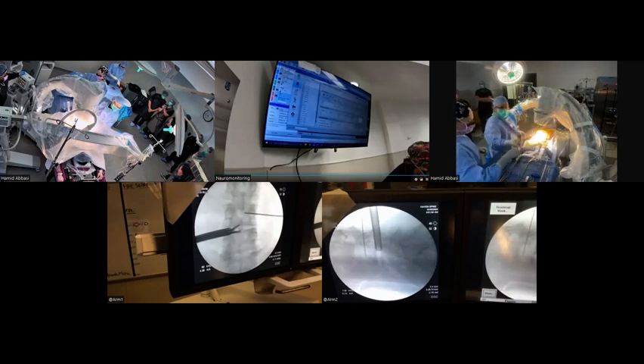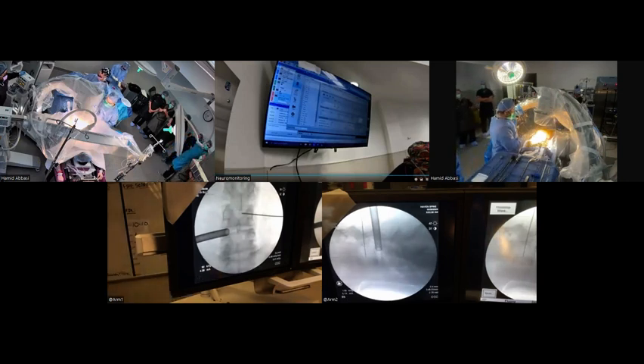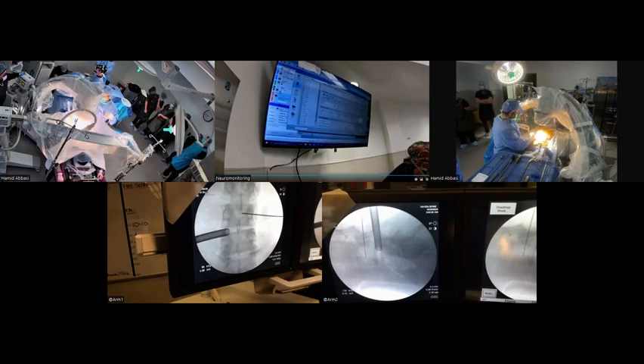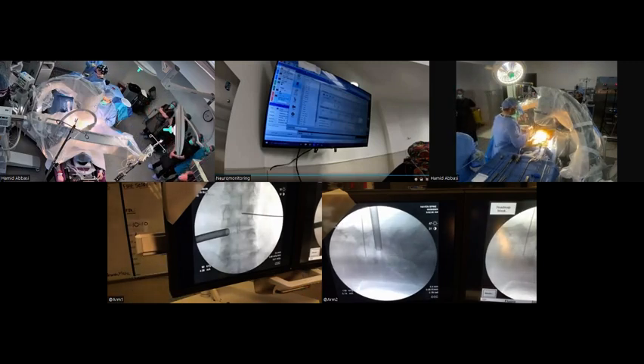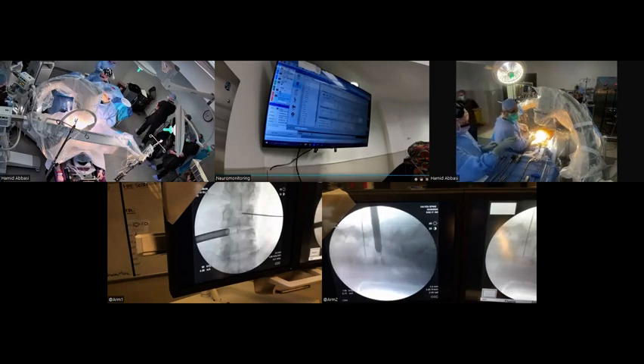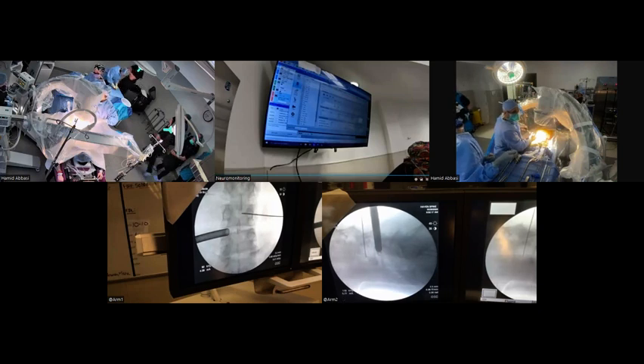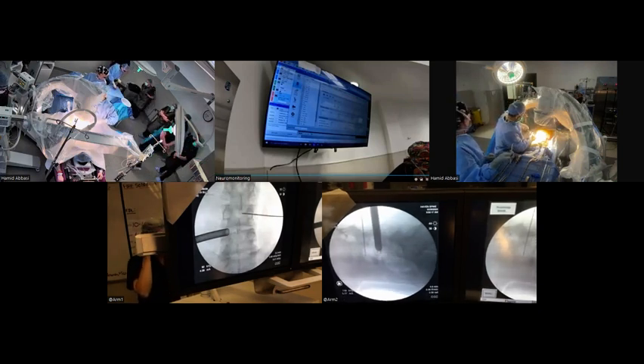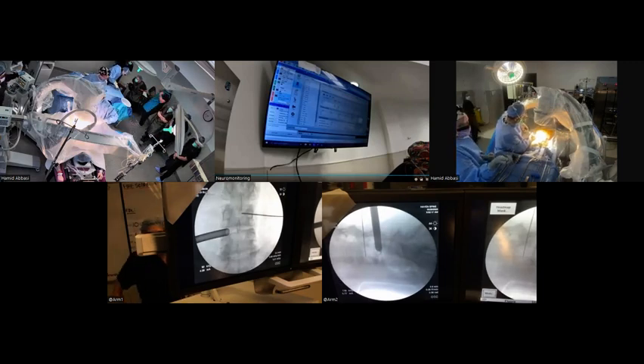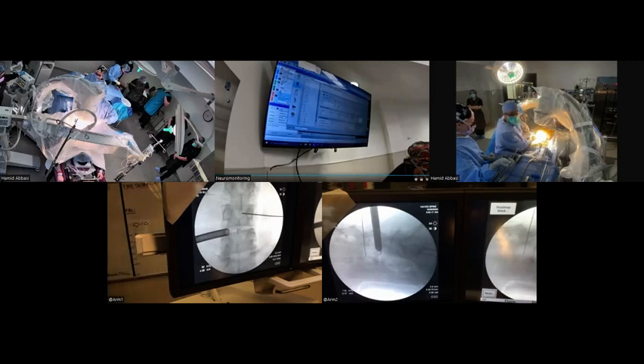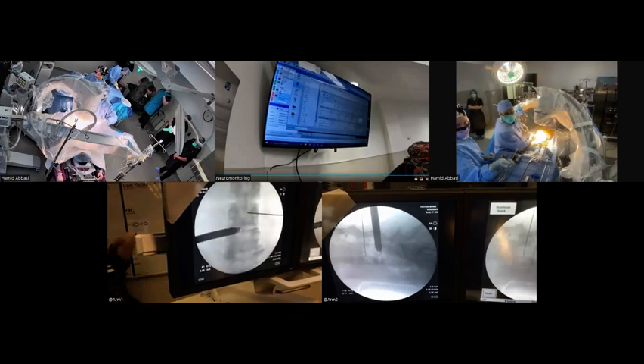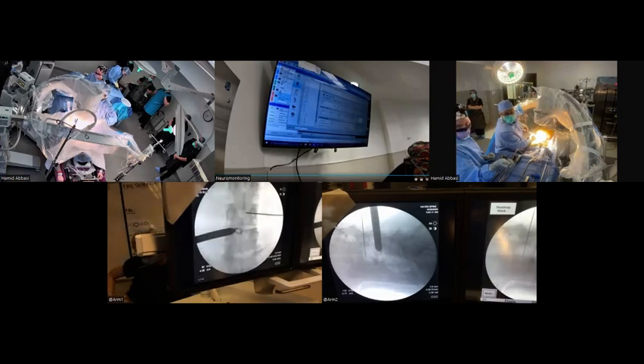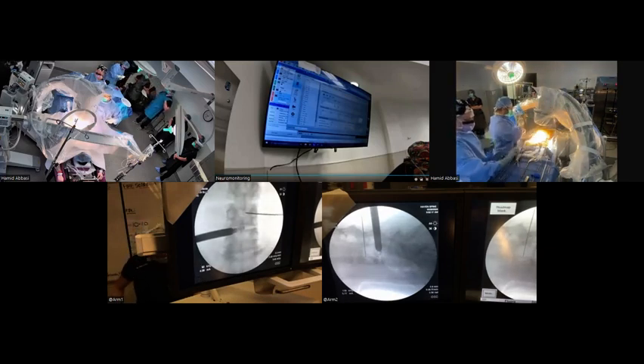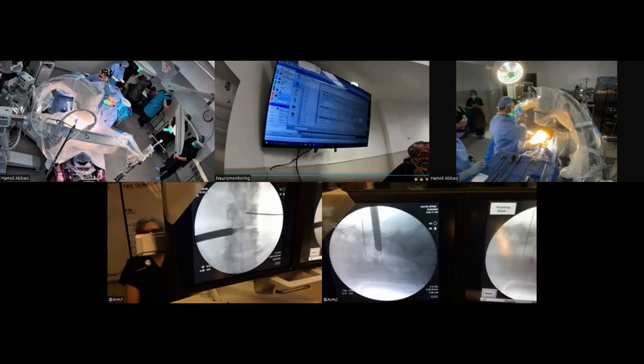This instrument that's being prepared is a flexible ring curette. It's a nitinol blade, super elastic. It goes in a collapsed position. The sleeve is open to deploy and expose the blade. The blade is used to scrape. The blade is capable of expanding to 13 millimeters off center line, so rotating the blade at a full expansion is not advised. The blade's intended to be a push-pull, like a ring curette, to be used in a traditional TLIF. Switching back to the pituitary rongeur to capture any fragments that were cut loose.